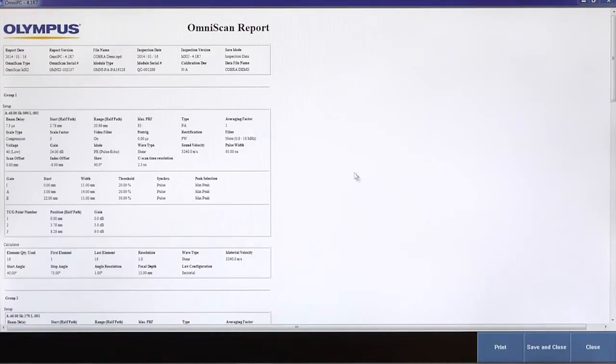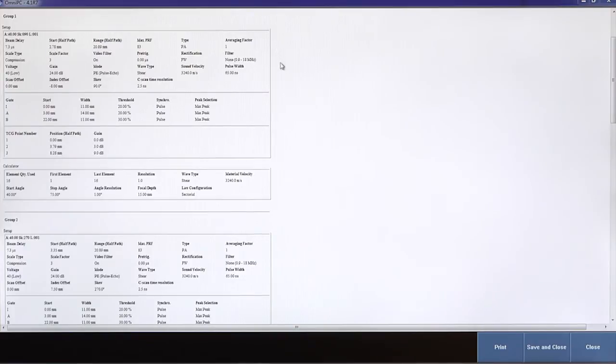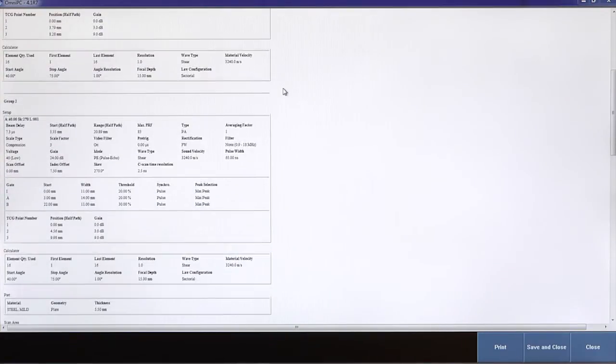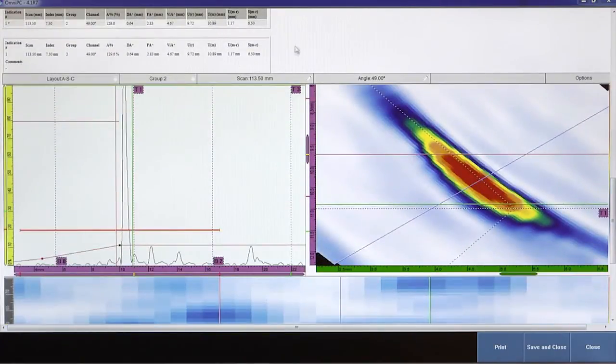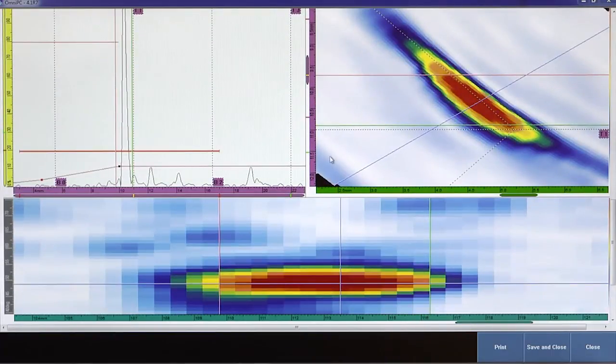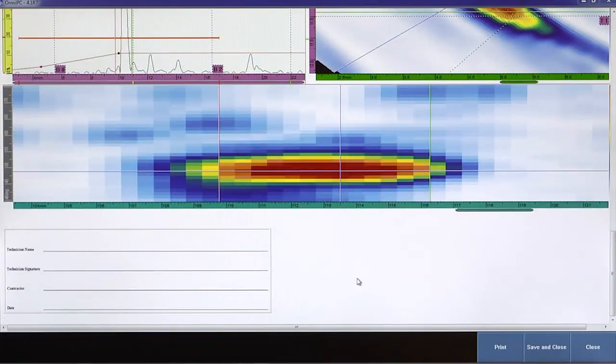From the report menu, information regarding the OmniScan, the calibration and the software, the setup and phased array setup for each group, the component and scanner information, and inspection results to include the statistical readings and a screenshot of the flaw. The report can be printed directly from here or saved and closed.